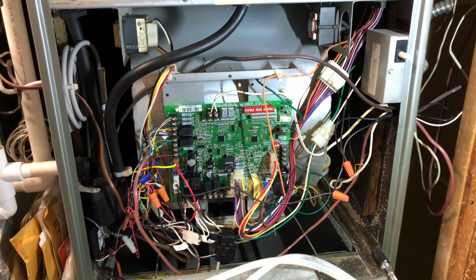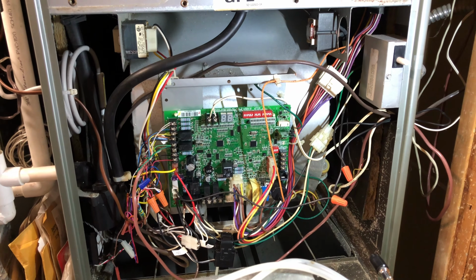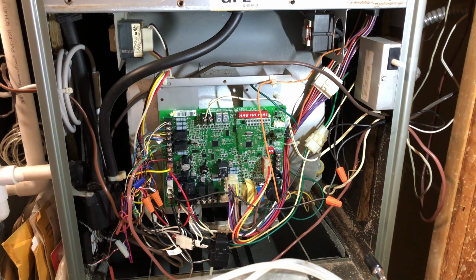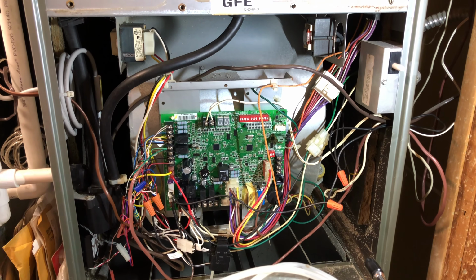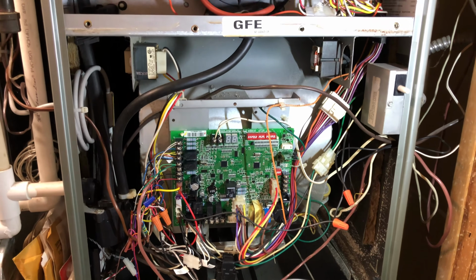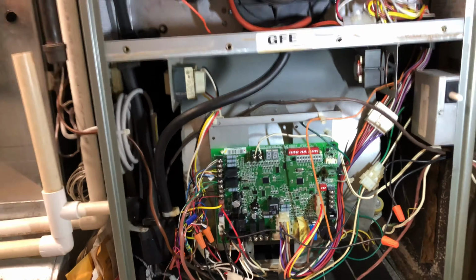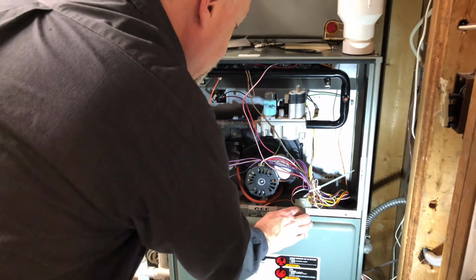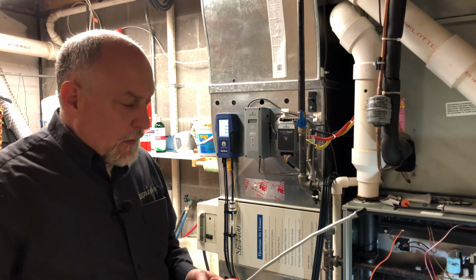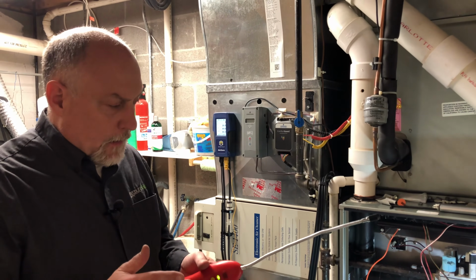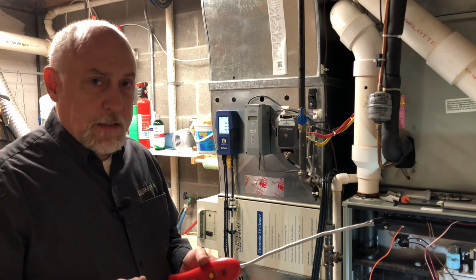Most of the time when you have a problem with a furnace, it's just due to loose connections or things like that. So we want to make sure that all that is done. And now all that looks pretty good on there. So we'll go ahead and we'll button this bottom door back up. And we're going to go ahead and get the top side ready for some measurements here. All right, so we got the blower door back on, and now we just want to do a quick little gas leak detection on here.